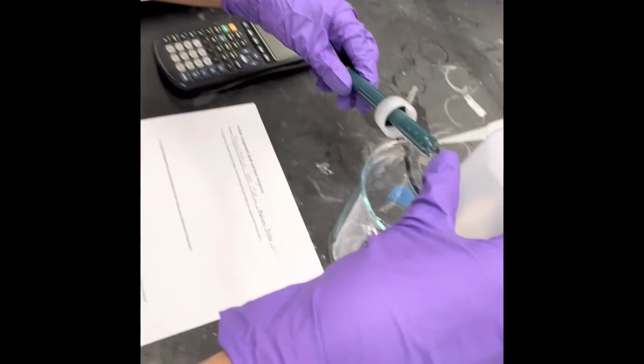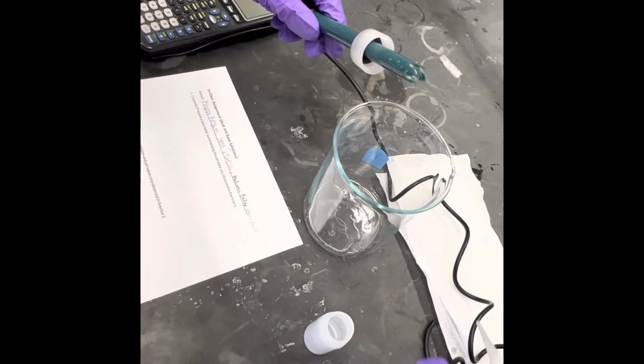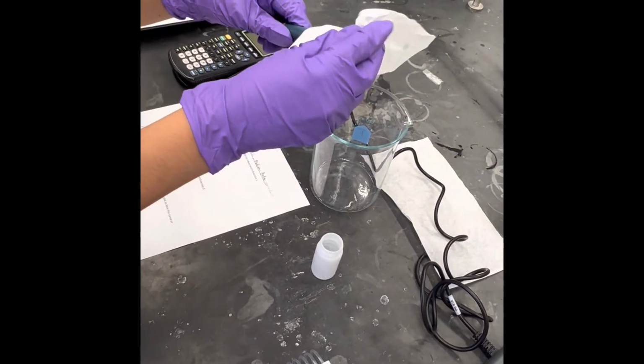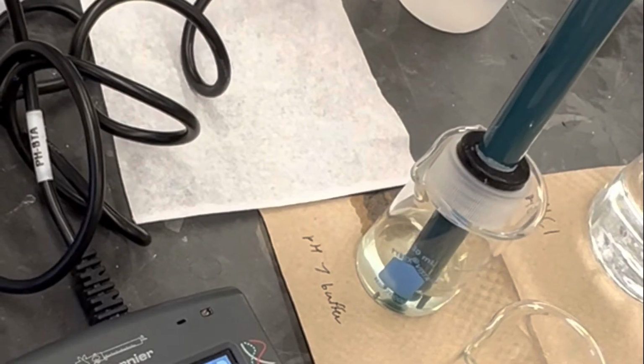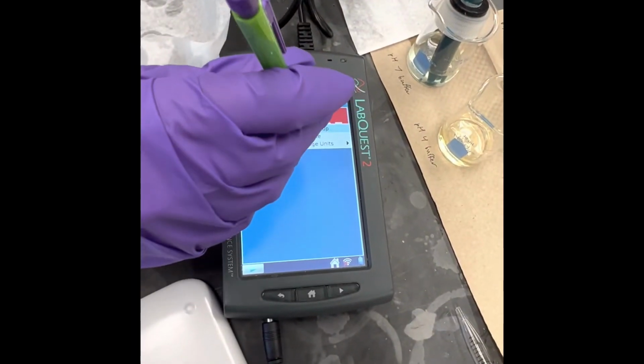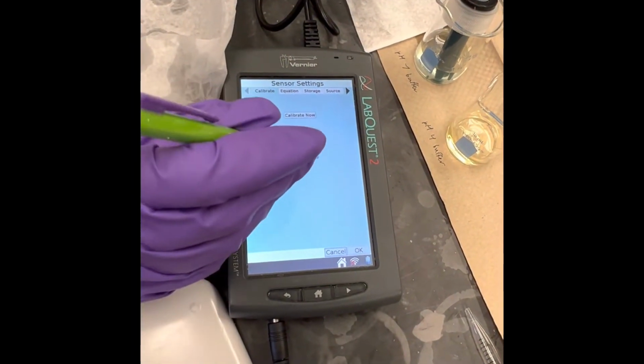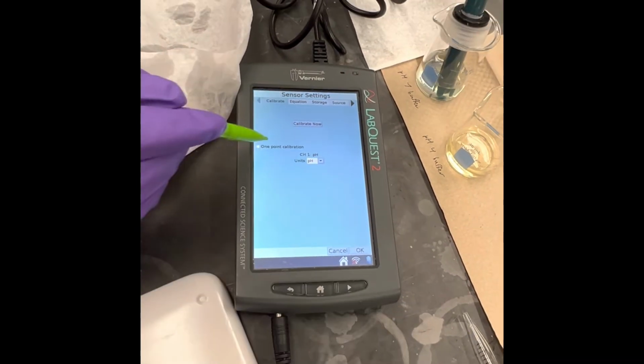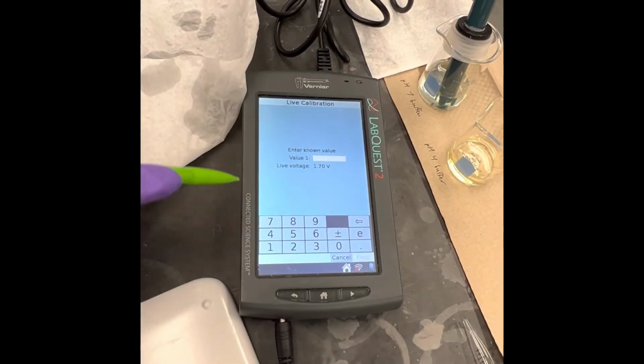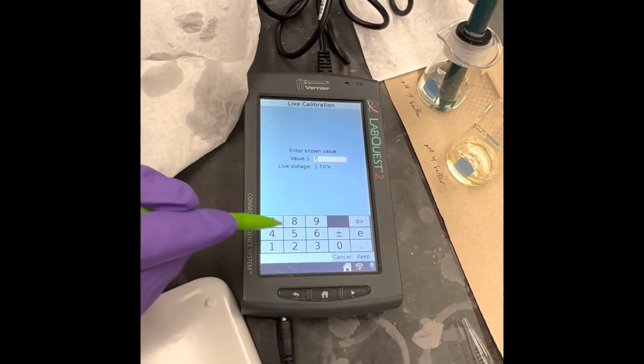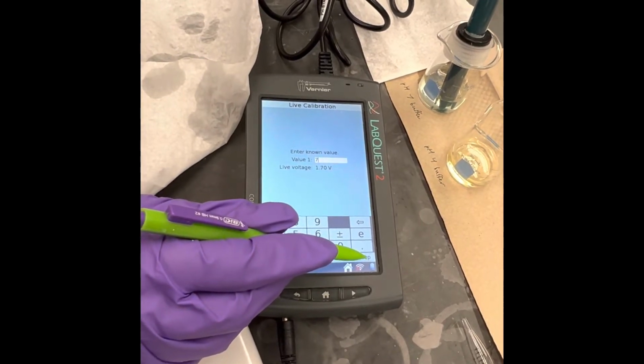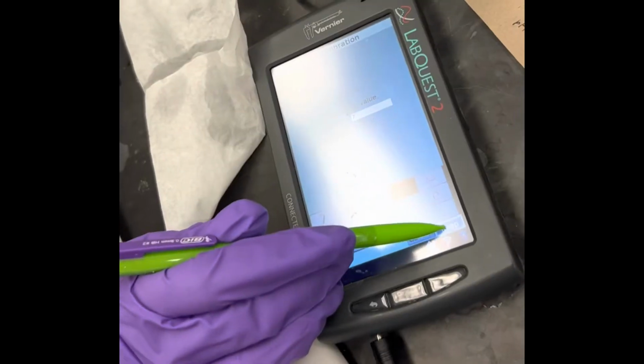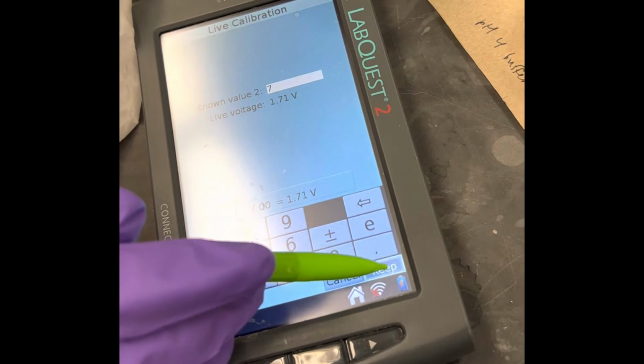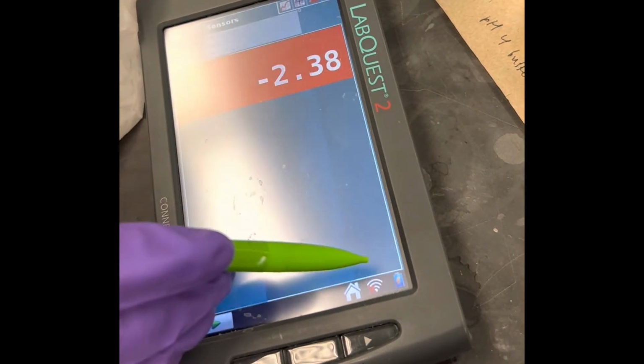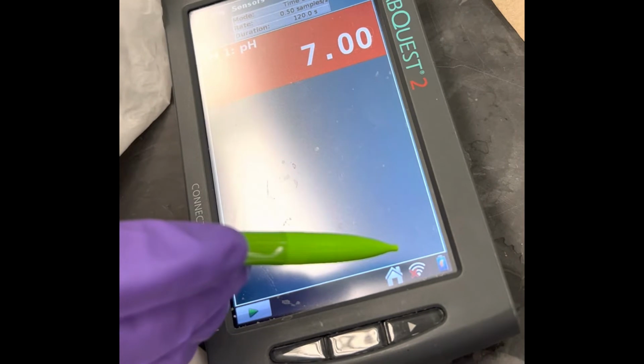Here, before taking the pH of our buffer solutions, we first have to rinse off the pH probe with water and gently dab it dry with a Kimwipe. Here, we are measuring our pH 7 buffer solution. But before we can take an accurate pH of our pH 7 buffer solution, we first have to calibrate the pH meter. When calibrating, the pH meter is going to ask us to plug in a number for the known values of 1 and 2, which happens to be our pH 7 buffer solution. After it is done being calibrated, it is now ready to take the pH of our first buffer solution.